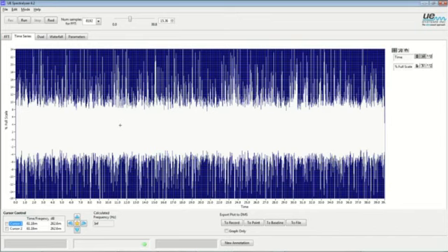The deeper or larger that the discharges get, the higher the intensity here. So we know we can look at this and see that there are discharges and they're not uniform in amplitude. That's one pattern or characteristic of a tracking event. And keep in mind, tracking is when you have these discharges along insulators.